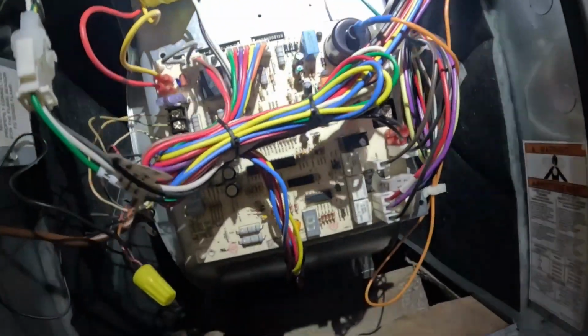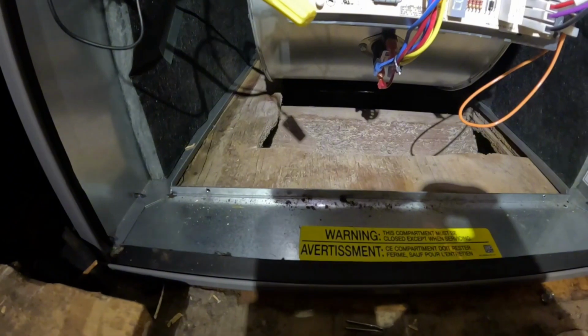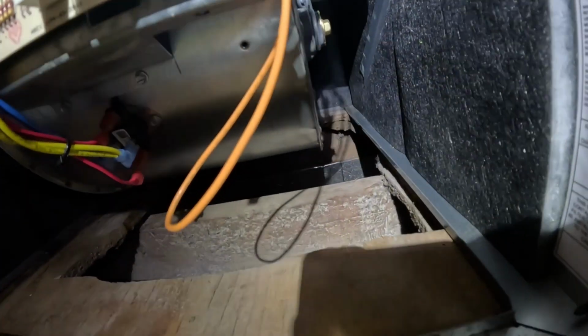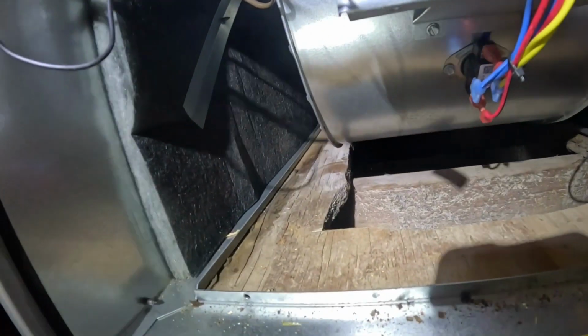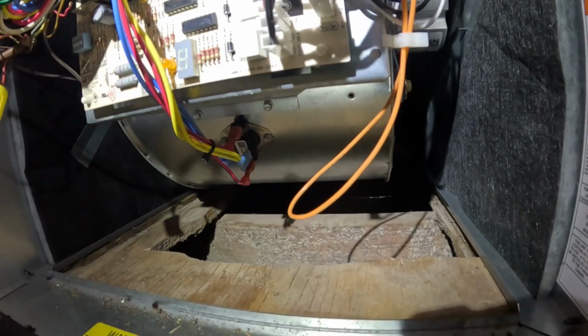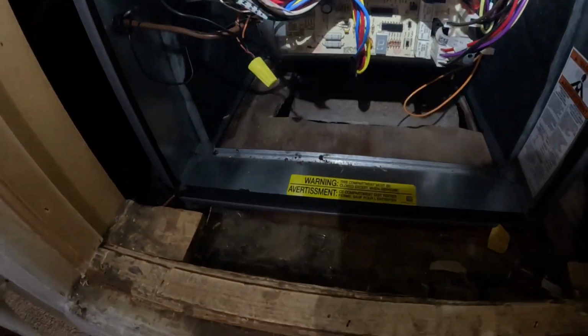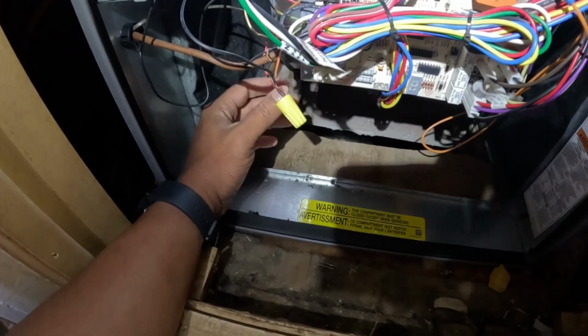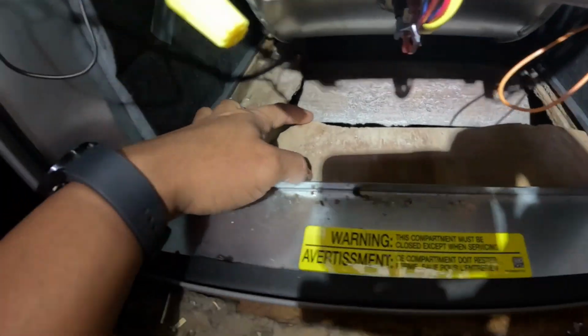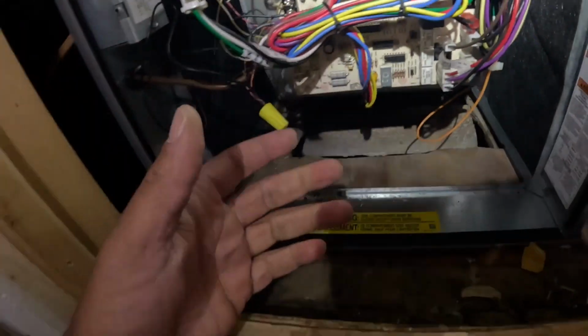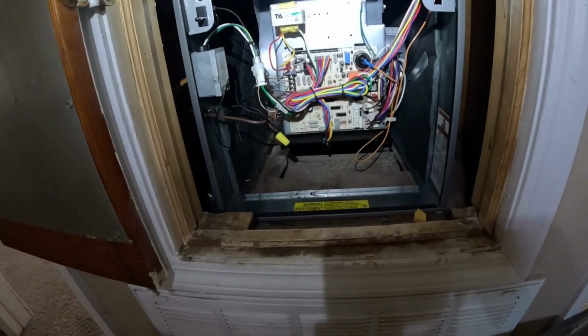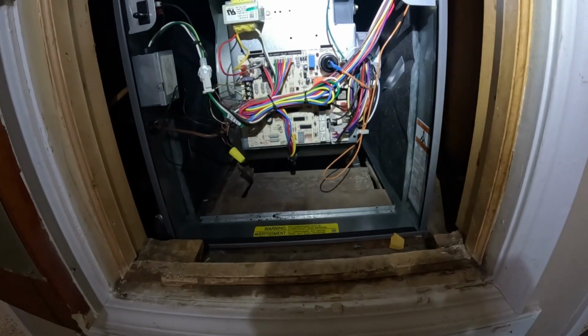I've had a couple instances in the past year finding fairly new installs where the bottom of the furnace is cut out for a specific opening, but the opening that's actually in here is significantly smaller. That's probably affecting airflow, I don't know how much. I might take a measuring tape to this and notify them, because I'm assuming the manufacturers designed the system to pull air through the entire opening. Shortening that, even to a small degree on all sides, even in the back, chokes the system down a bit, and that can probably create some issues. I just don't know how severe.